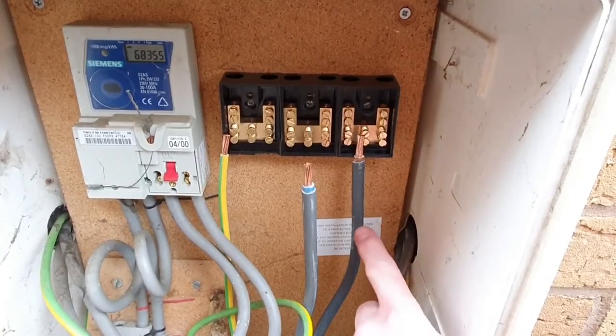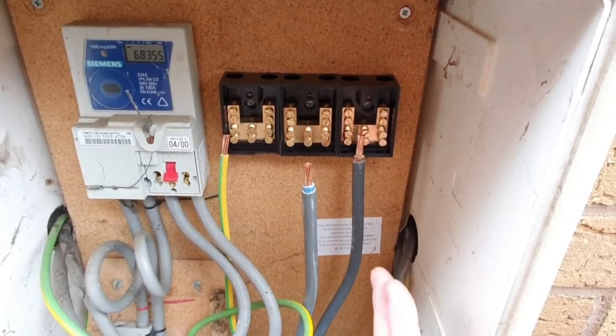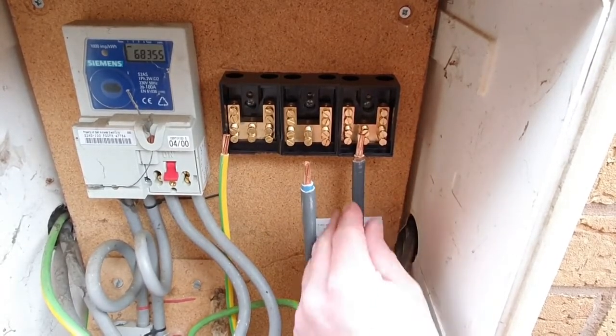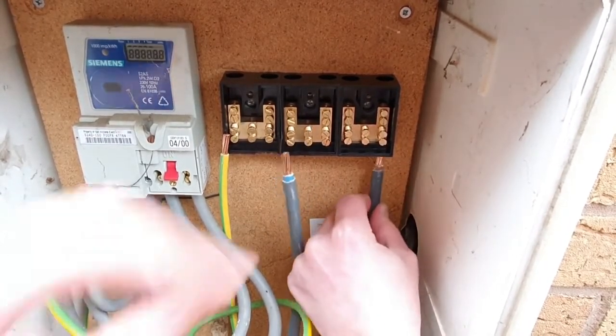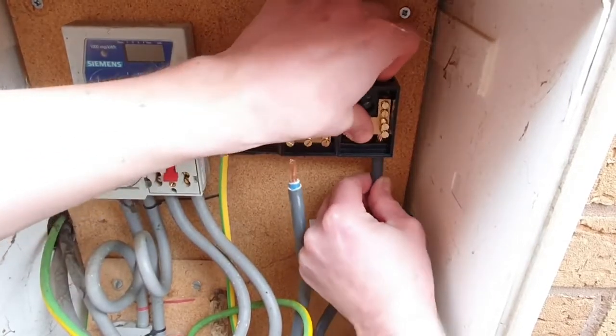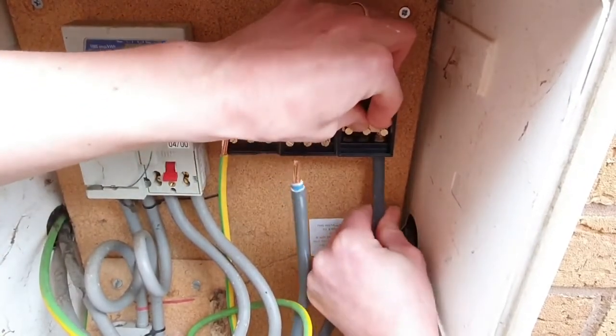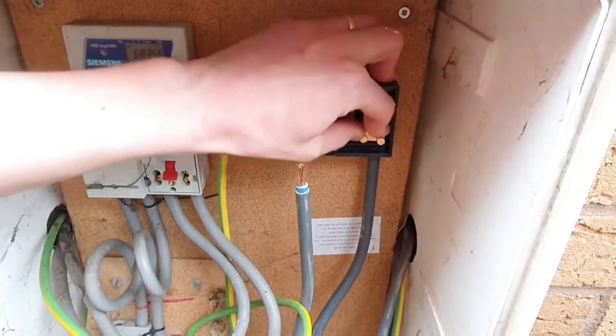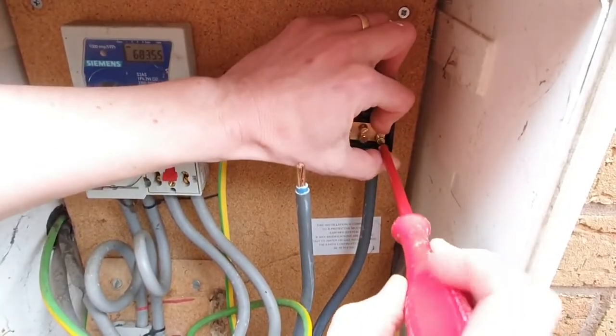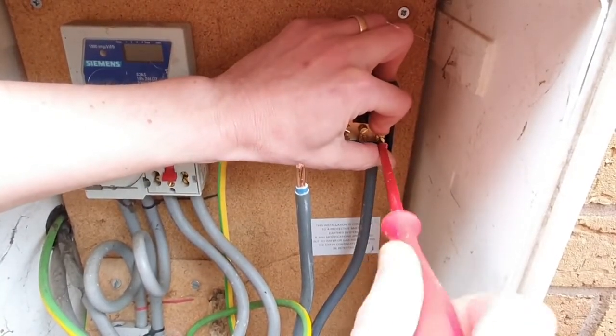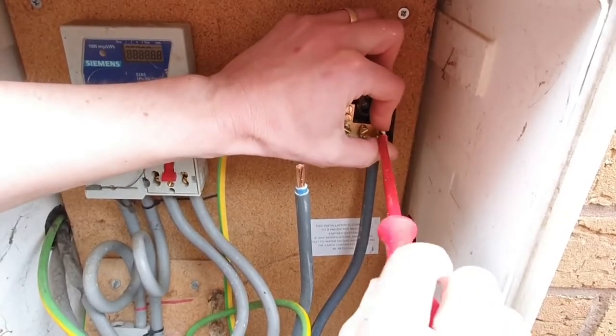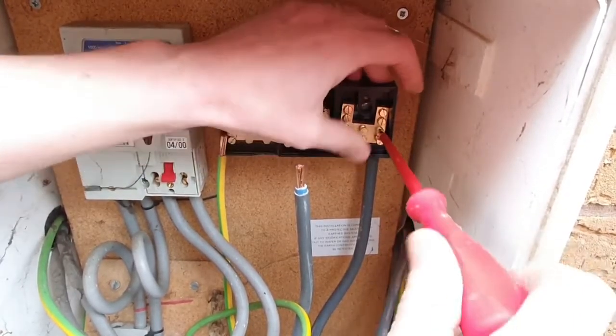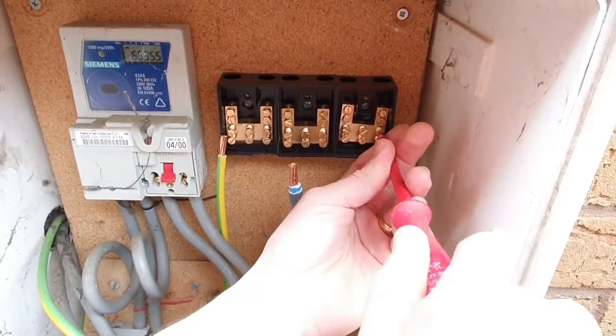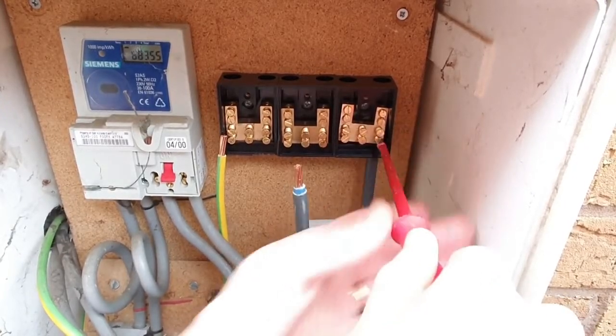Okay then, so this is our line, neutral and earthing conductor for our new consumer unit that we installed within the installation. We'll look at that again later on. These are a little bit fiddly here, Joe, in order to poke these in. So we want to push that down for us. Okay, I think we can connect those up then. Absolutely, so we'll get that tightened up in there. And that's our line conductor connected out to our new consumer unit. And then we're going to put the neutral in.